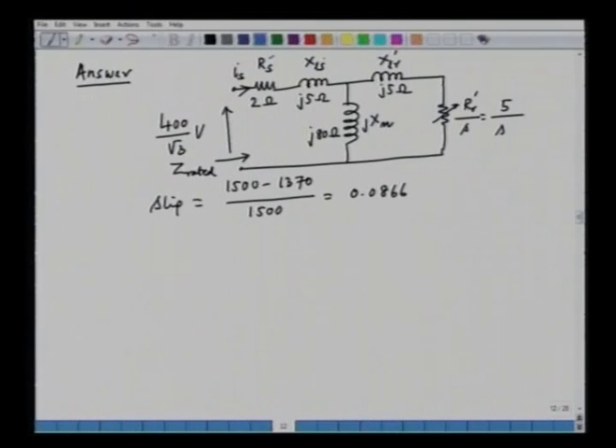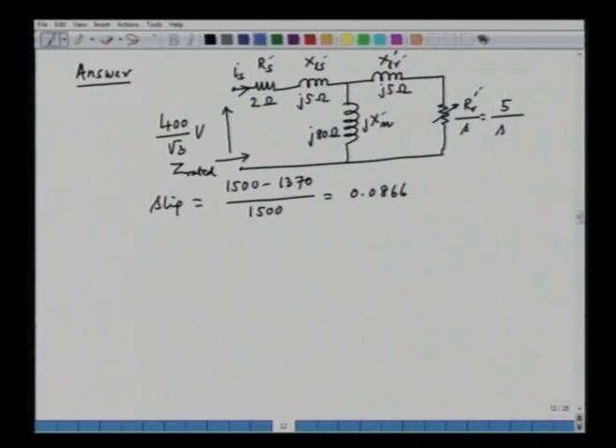A steady state per-phase equivalent circuit will be sufficient to analyze the various currents and voltages. We have the well-known per-phase equivalent circuit of an induction machine in steady state. It consists of the stator resistance, the stator leakage reactance, the rotor leakage reactance referred to the stator side, the rotor resistance, and the magnetizing reactance. The motor is star connected, so the per-phase rated voltage is 400 divided by root 3.